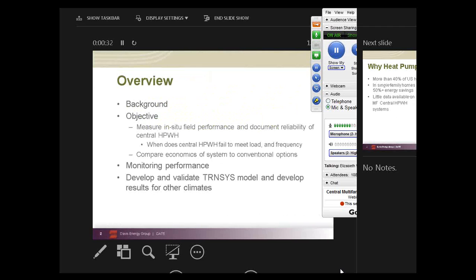In the background, I'll lightly go over the history and reasons for central heat pump water heaters, the site project, and system configuration. Our objectives for the project were to measure the field performance and reliability of a central heat pump water heater, most notably how often the heat pump water heater meets the load, and under what conditions it needs backup. We then wanted to compare the economics of running the heat pump water heater system to conventional electric storage and natural gas storage options. I'll go over the observations we made during the monitoring period and how we took the monitoring data and developed a heat pump water heater model in TRNSYS to perform the economic comparisons.